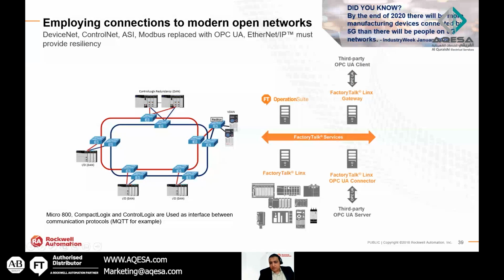That's for high availability. What about for Rockwell products hardware? We will use FactoryTalk Linx, formerly known as RSLinx Enterprise. For third-party OPC UA or DA, for OPC UA we will use FactoryTalk Linx OPC UA Connector. For the upper level, SCADA or IoT platform, we have another small software called FactoryTalk Linx Gateway for third-party UA. Of course we have a solution for OPC DA, but OPC UA is the future because it is the encrypted version of OPC. Don't forget that our Micro800, CompactLogix, and ControlLogix support MQTT for IoT platforms, so if you have any MQTT broker and want to communicate with our PLCs, it can do it directly.